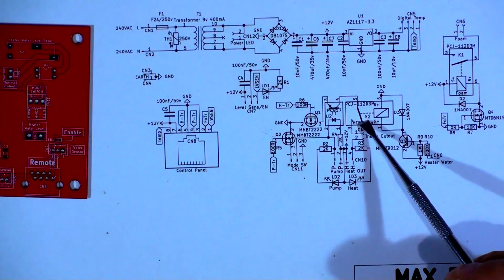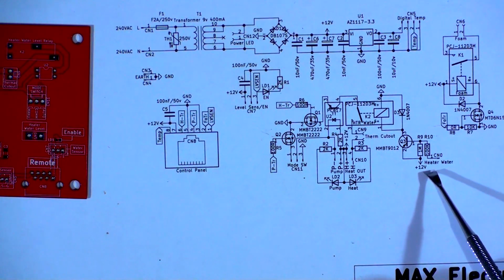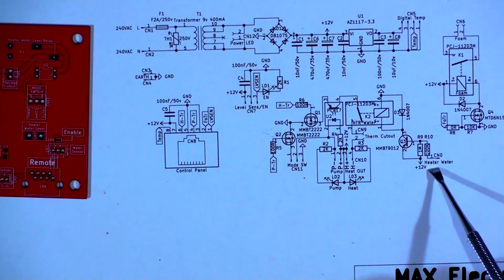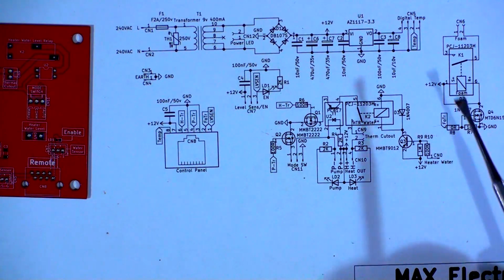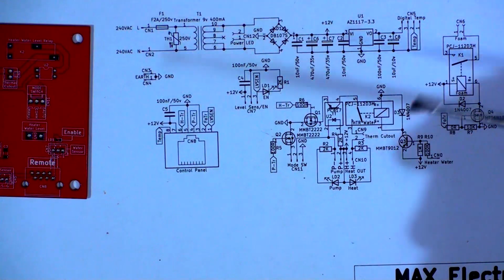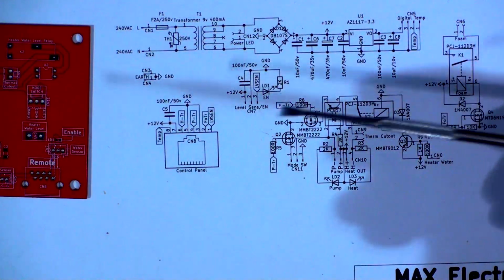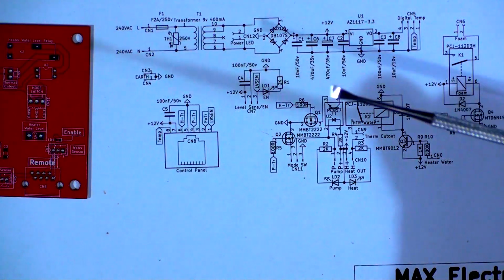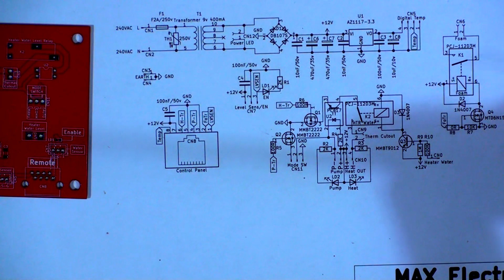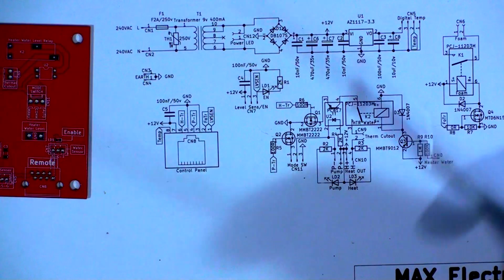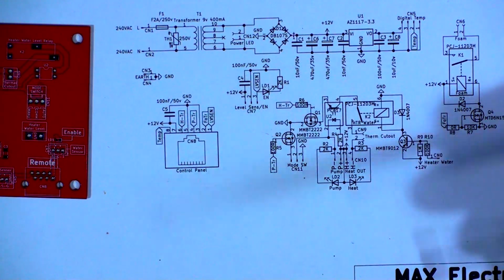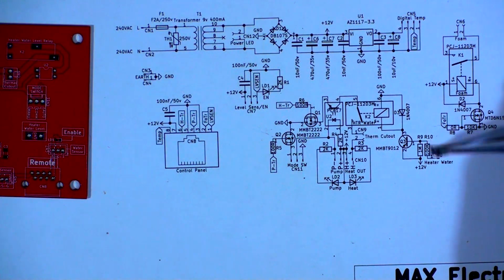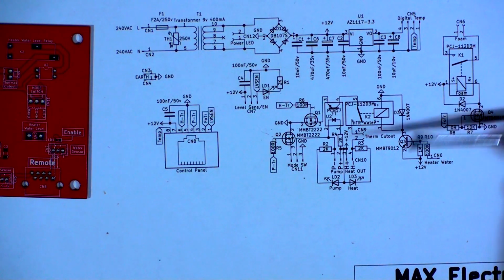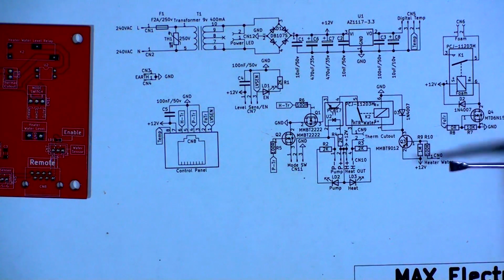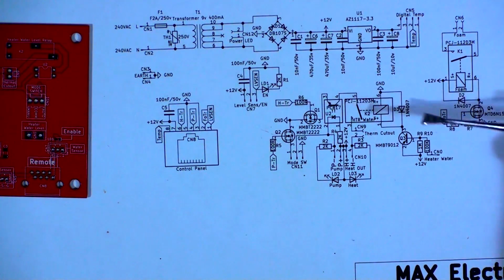And the relay has to be on, and is triggered by the water heater level sensor. So what that is, it's actually just a rod that is generally in all the spa water heaters that sticks out next to the heating element, and it's connected to here. And it responds to ground, so if there is no water in the actual heating chamber, it will not ground. That's connection 0, and therefore it will not trigger the relay. So once the water is shorting out between ground and that pin, it will trigger the relay.